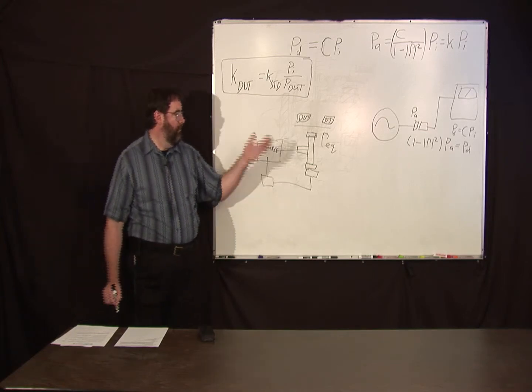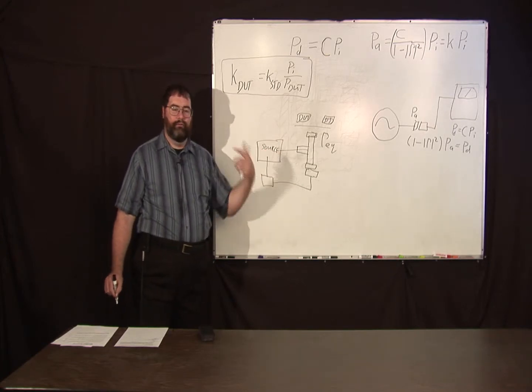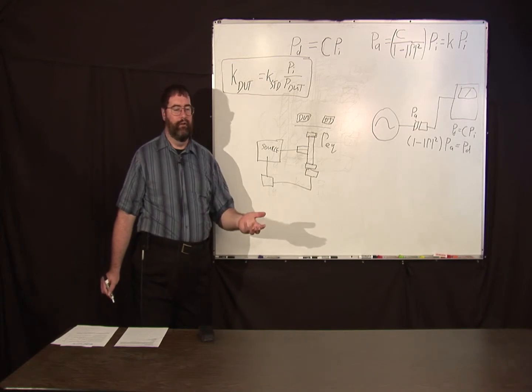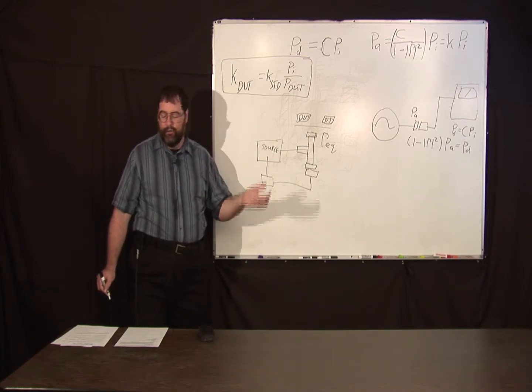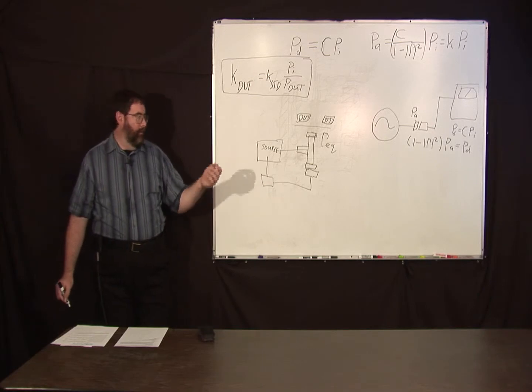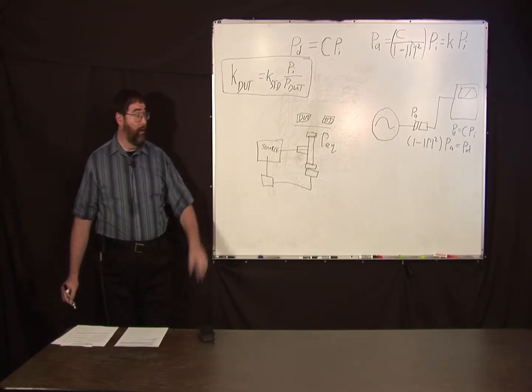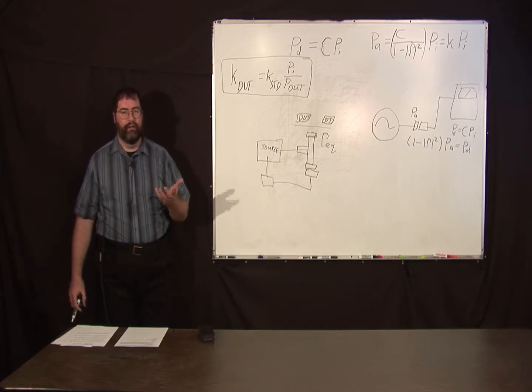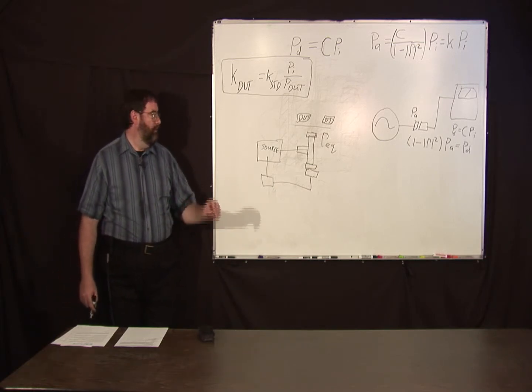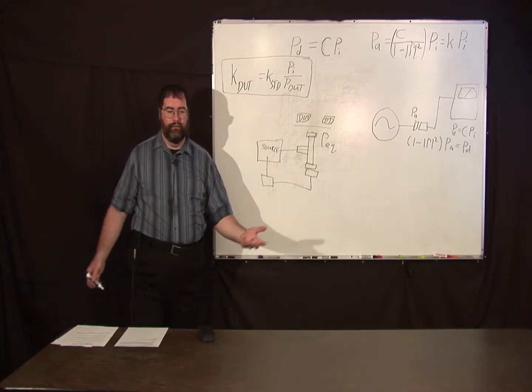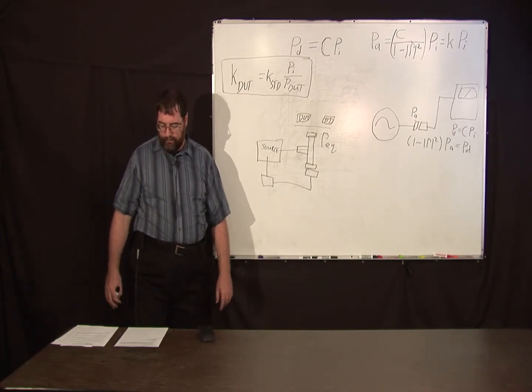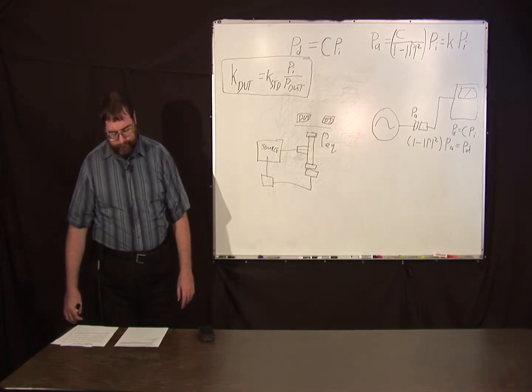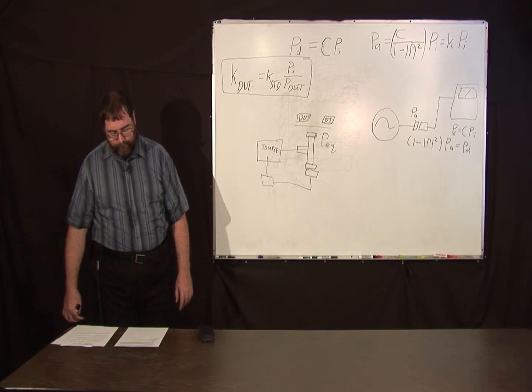So then you can put your alternate connection between your DUT and your standard and get a much better calibration transfer. Because one of the things you know is calorimetry, as you probably can guess, is an expensive way to calibrate something. This is a much cheaper way to calibrate something, so that you have a traceable power measurement back to, in this case, current's an SI unit, so it's back to primary standards for current. Maybe some voltage standards at a high level. And through thermometers, Kelvin is a base unit that you can get traceable back to your national lab, or back to physical constants.